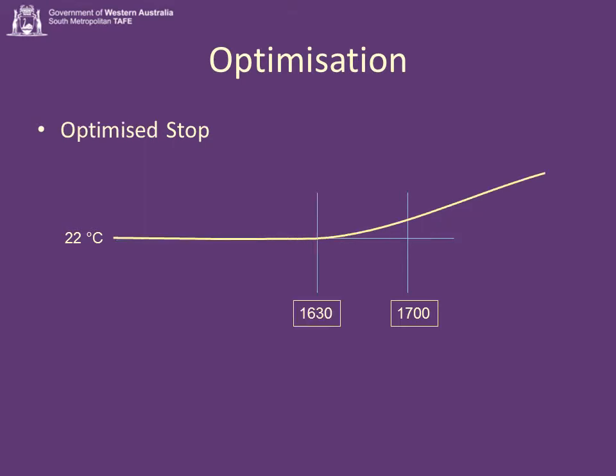With a networked system, we can do optimize stop instead. We continue running the air conditioning units, but turn the big plant - the chillers and boilers - off early, maybe at 4:30, depending on the outside air temperature. The temperature in the building will start to rise, so by 5 o'clock it's a little warm, but that's fine since people are leaving anyway. This saves another half hour of running the major plant - a huge cost saving.